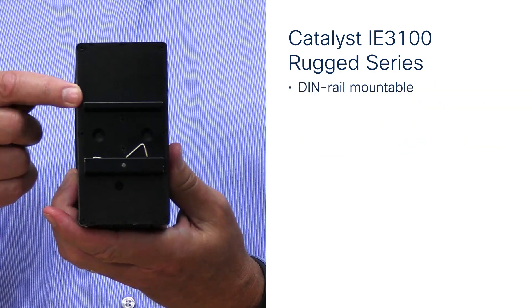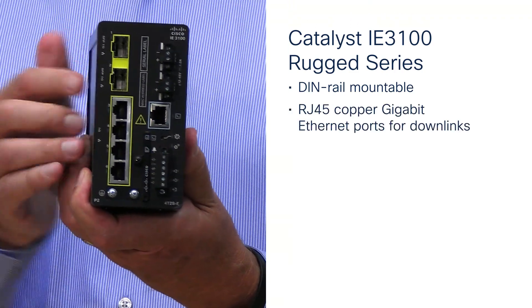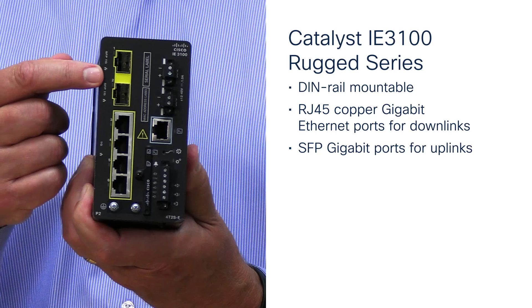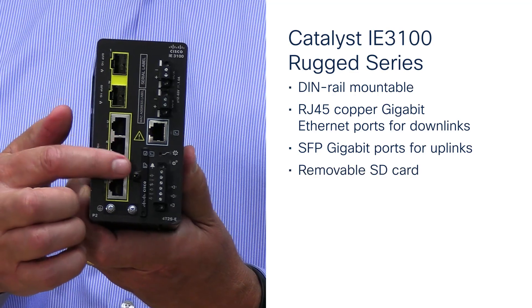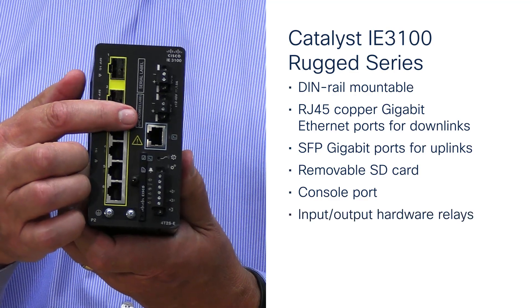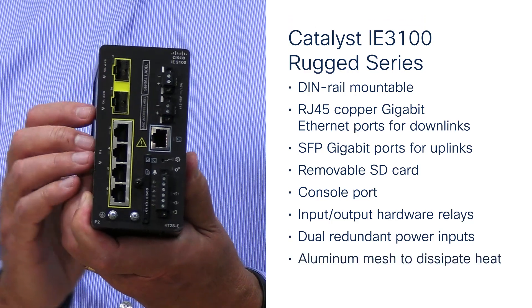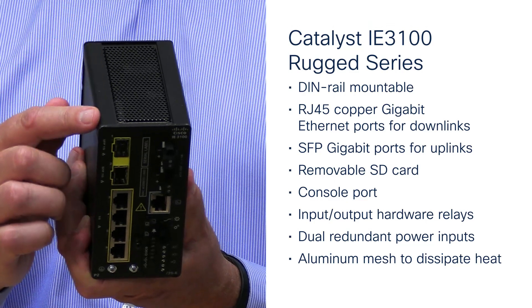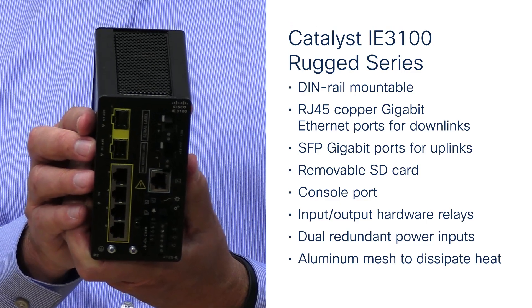It's DIN-rail mountable — perfect for replacing those small unmanaged Ethernet switches. These are the four RJ45 copper Ethernet ports for downlinks and these are the two by one gig SFP interfaces for uplinks. Other features to note on the face plate: support for a removable SD card for extra storage, the console port, the input/output hardware relays, and dual redundant power inputs. All IE3100s have an aluminum mesh top and bottom allowing heat to dissipate easier. The mesh design is how the 3100 can be the smallest DIN-rail managed industrial Ethernet switch.